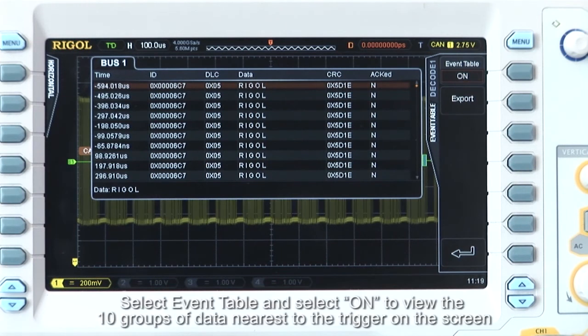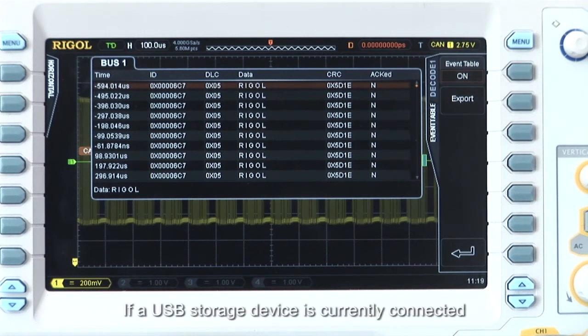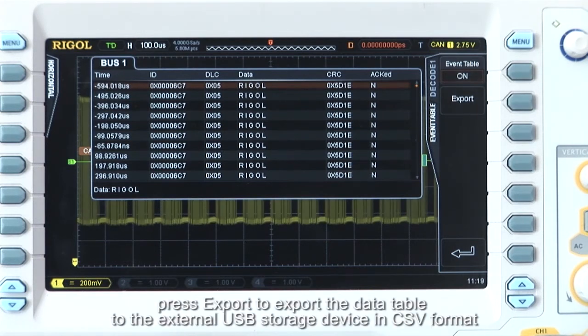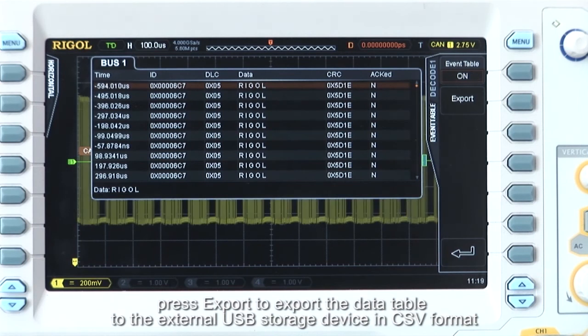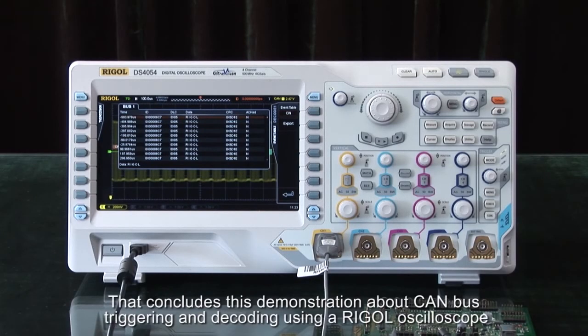Select event table and select on to view the 10 groups of data nearest to the trigger on the screen. If a USB device is currently connected, press export to export that data table to the external USB storage device in CSV format.